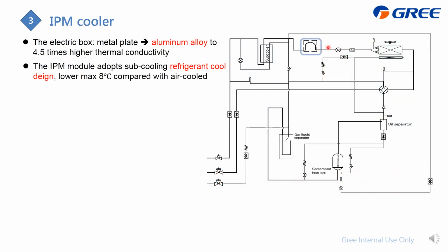IPM cooler located here. Because we apply the inverter compressor, and lots of the heat will generate from the compressor IPM, and we apply the refrigerant to cool it down. So just compare with the air cool, it is max 8 degrees will be lower. And what we call is subcooling. It is because at this part it is completely liquid, either heating or cooling.